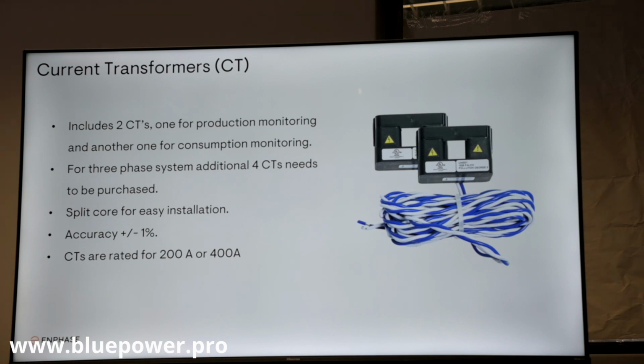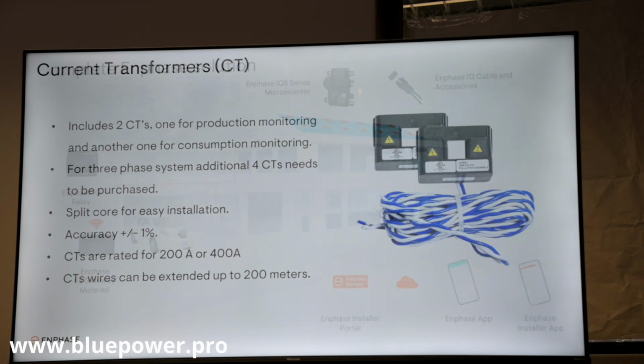And what's not shown here is that the CT's wires can be extended up to 200 meters, which is actually nice. I don't want to mention other products, I don't think it's fair, but some of the CTs we get in other installations have a limitation on the distance, which is sometimes a pain, because now you have to put the inverter next to the DB board, and there's not always space or capability for that.